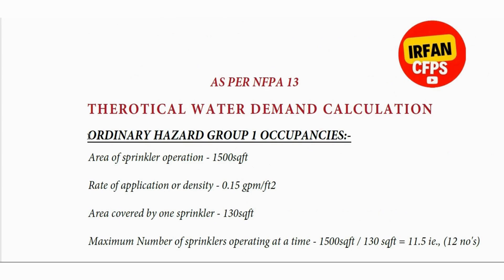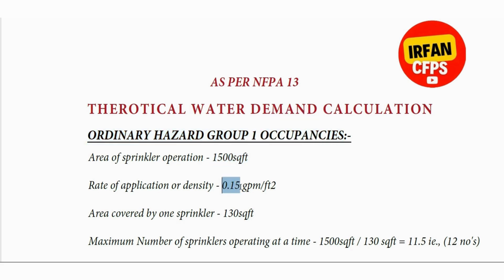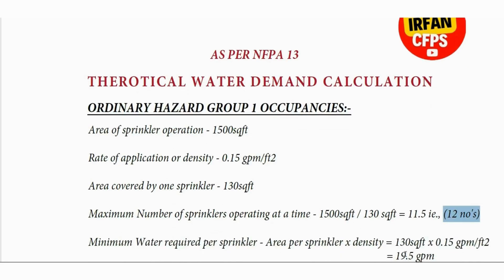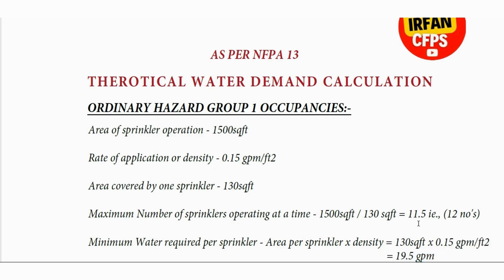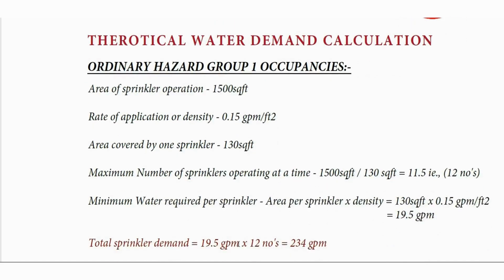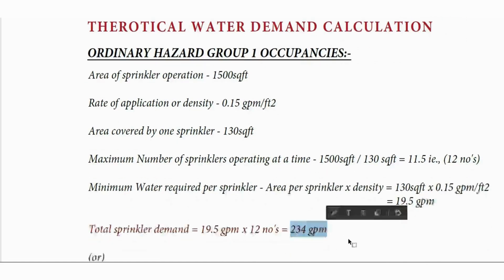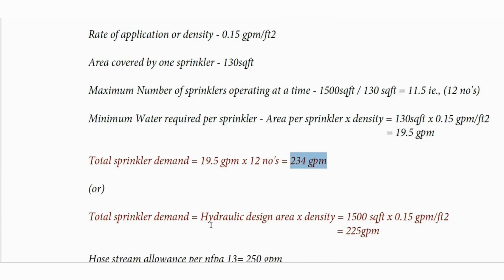Similarly, we calculate the theoretical water demand for ordinary hazard group 1 occupancies. For NFPA 13, the area covered by one sprinkler for ordinary hazard group 1 or group 2 is 130 square feet. The maximum number of sprinklers will be 12, and the minimum flow required from one sprinkler is 19.5 GPM for ordinary hazard group 1. The total sprinkler demand will be 234 GPM.